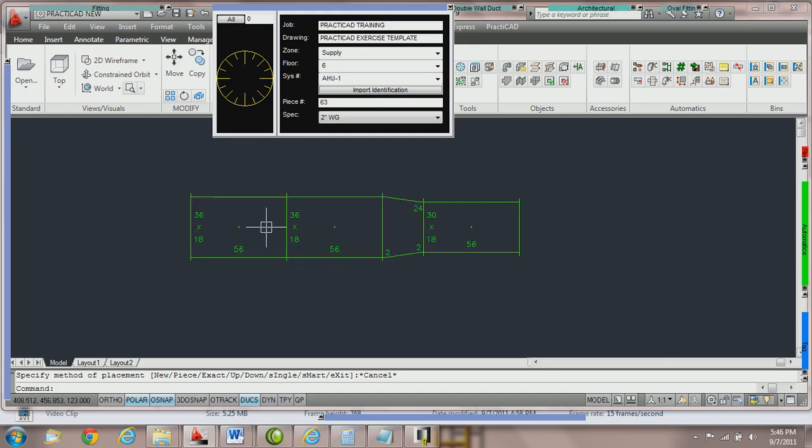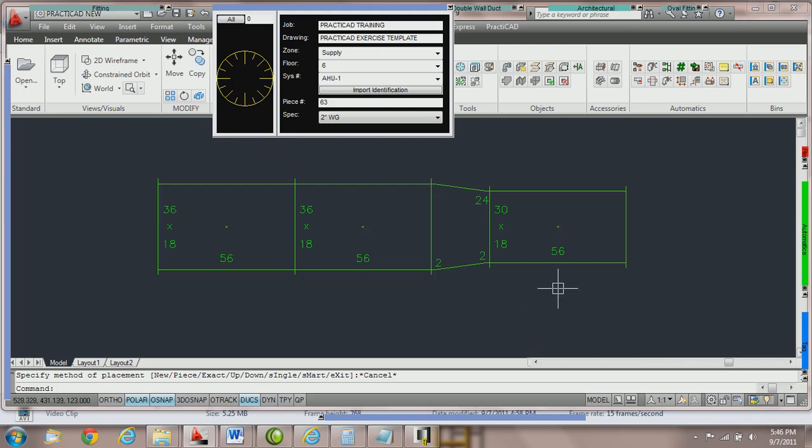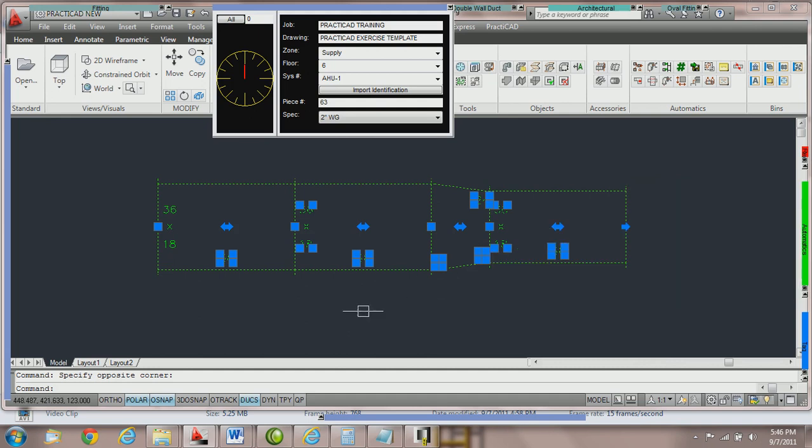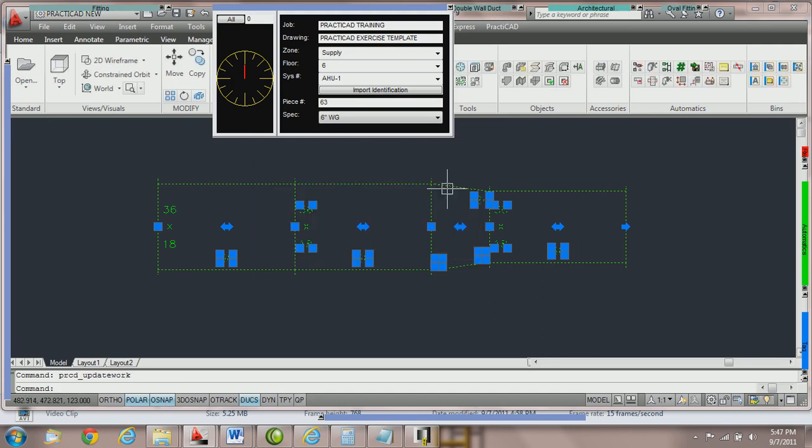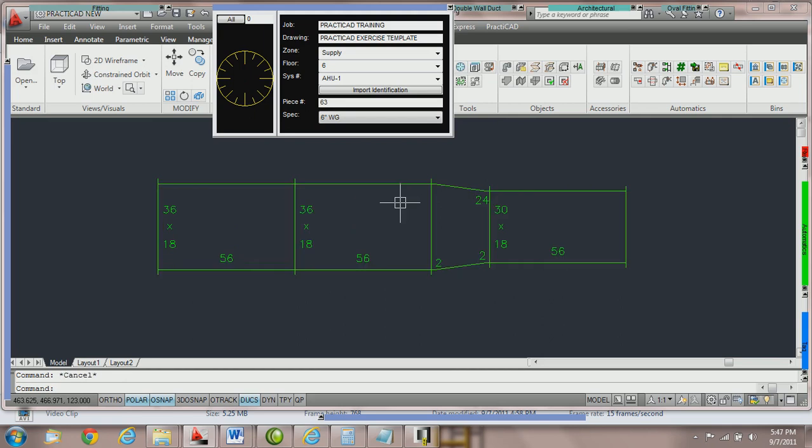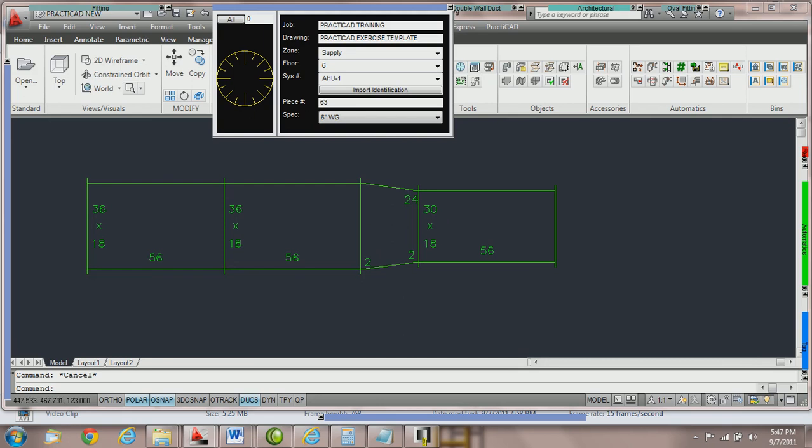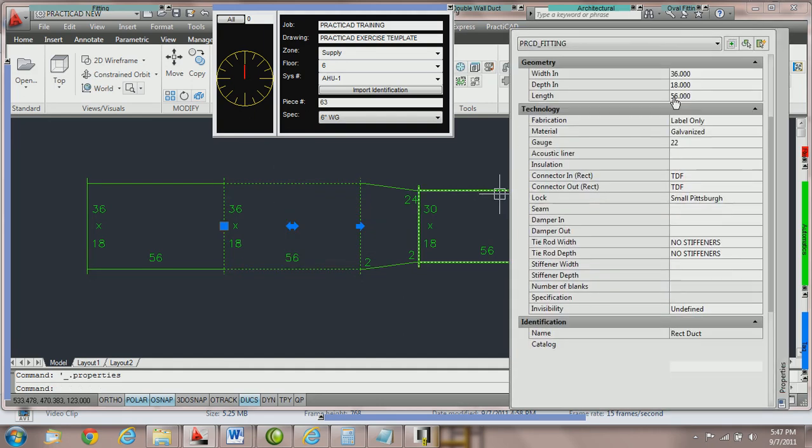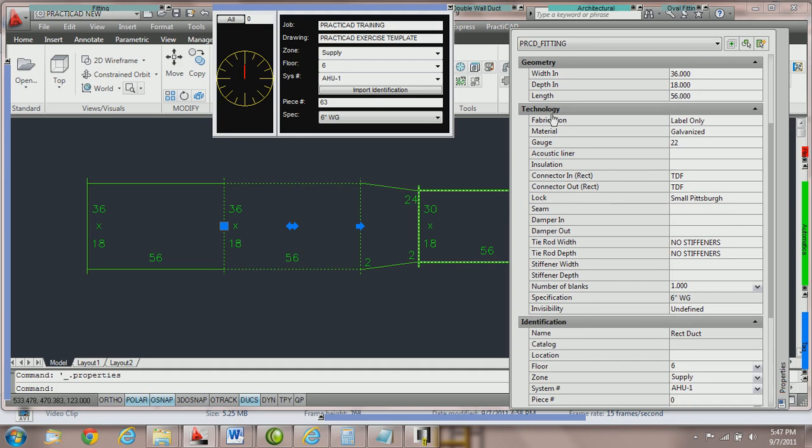Now if we're going to edit this, we could highlight this section or use a selection automatic. There are separate tutorials on all of these selection automatics. Then we can go to the workbox and apply six inch water gauge to the currently selected duct. When I press OK, you'll see when we let go of these fittings that they no longer have tie rods because the spec has changed. If you double click on a fitting and go into the AutoCAD property box, underneath technology we show the specification of the fitting itself.